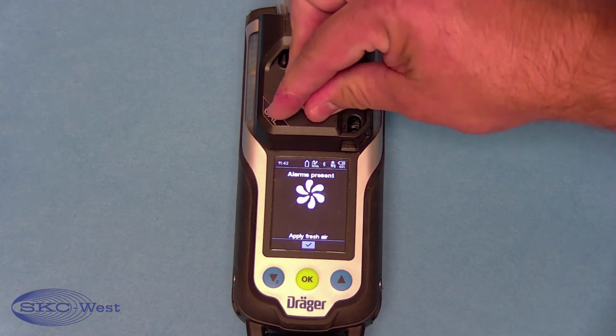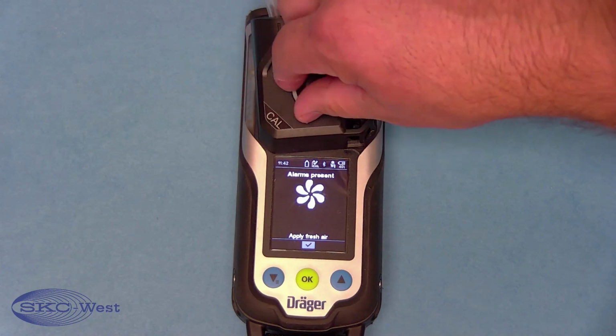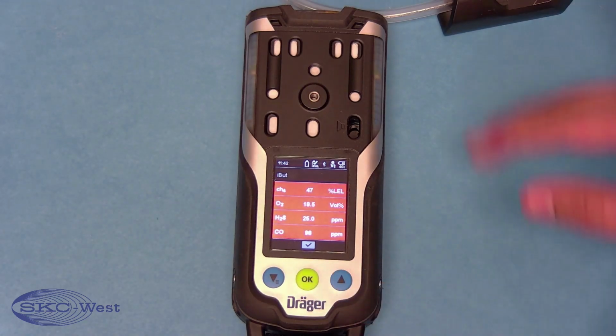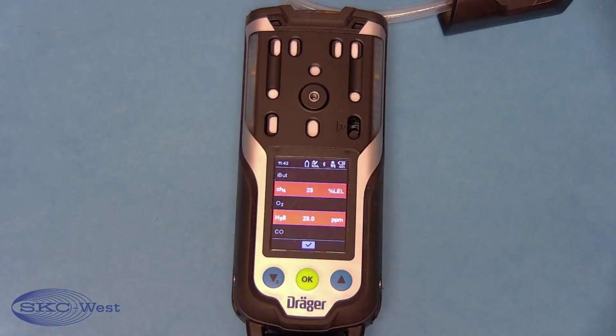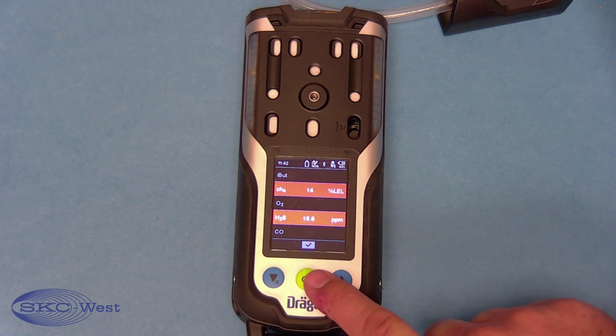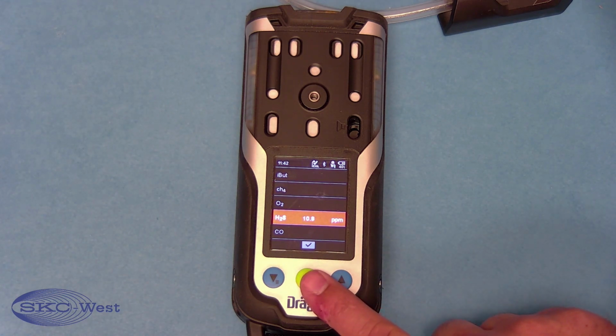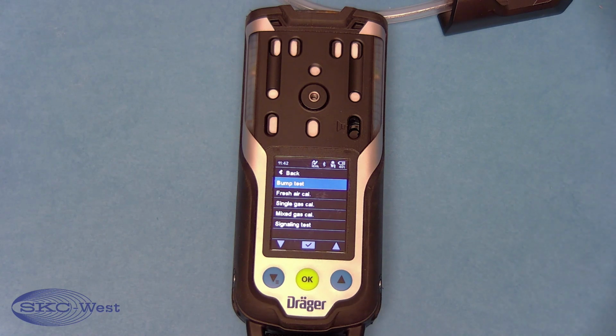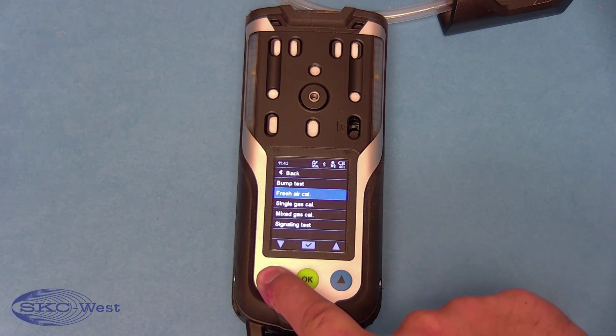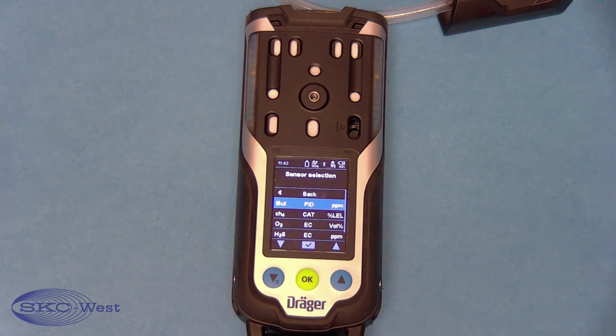It's going to tell you to apply fresh air. You can unscrew the calibration adapter, wave your hand over the sensors, and press the OK button. Once everything stabilizes back down to 0, you can press the check button. Now it kicks us back to the screen we were just on. So for instance, if you have an additional sensor in there or you needed to calibrate single gas calibrations, you would arrow down and highlight the single gas cal, hit OK, and then you'll select whatever sensor you want to calibrate.